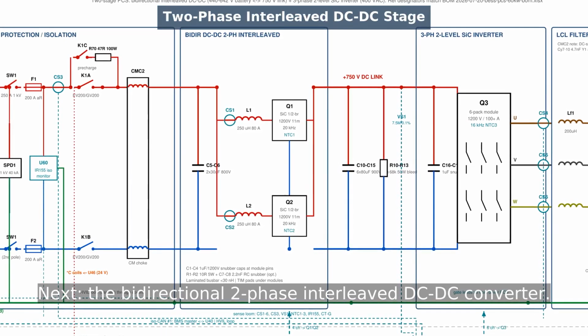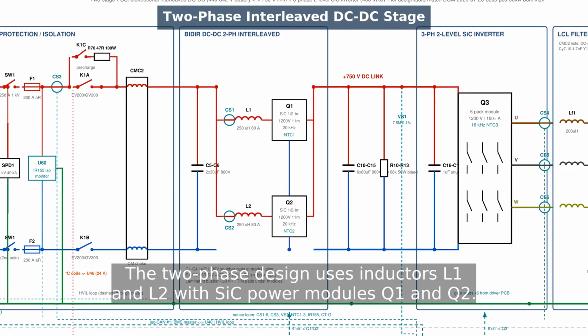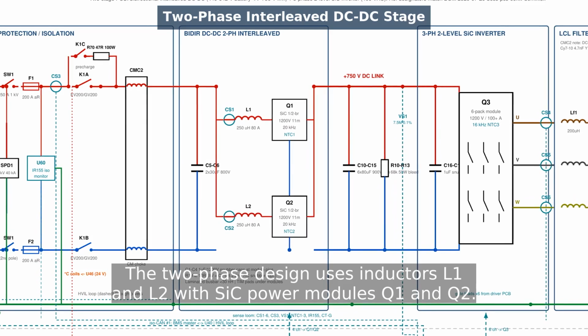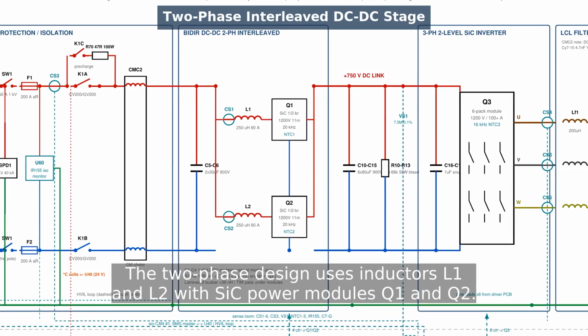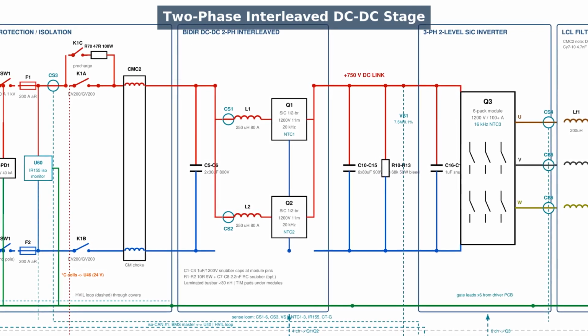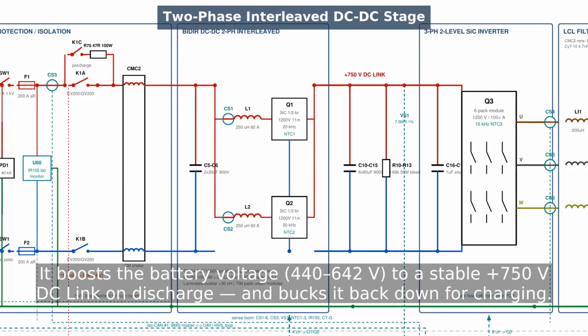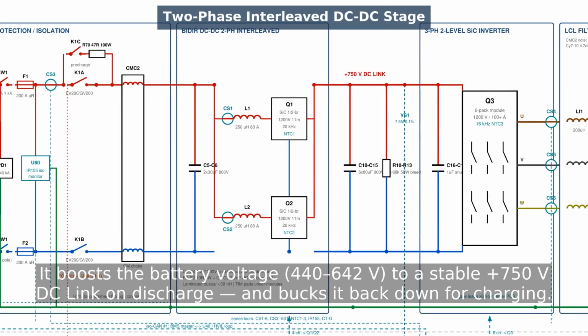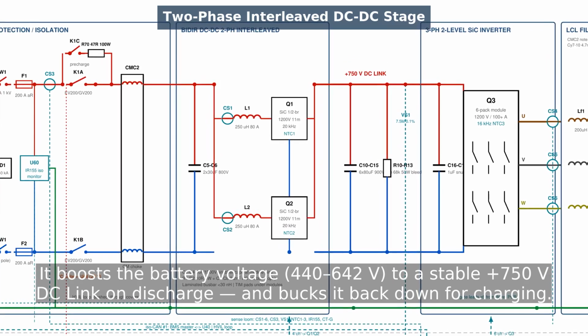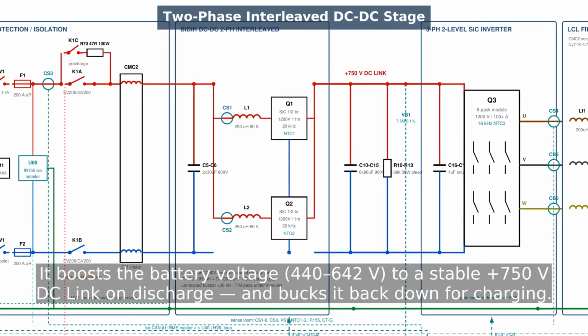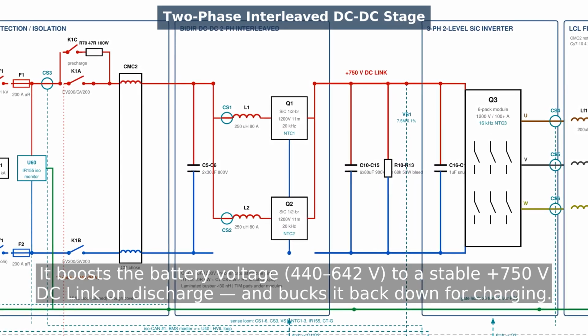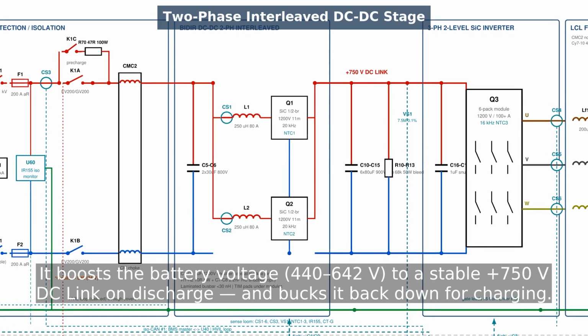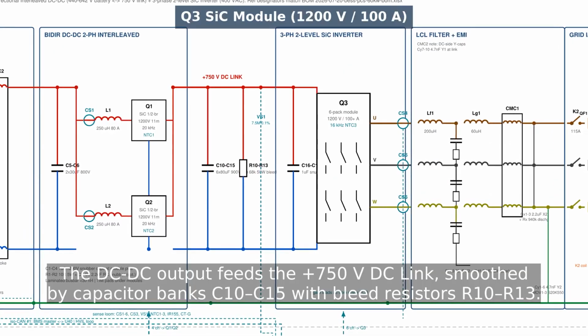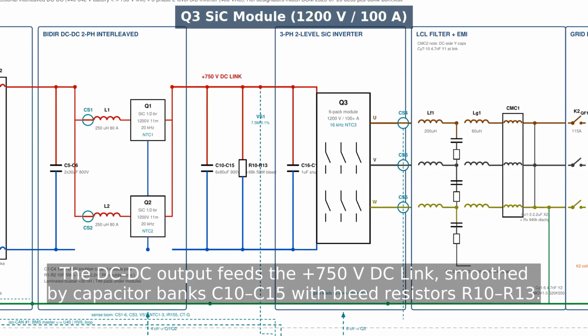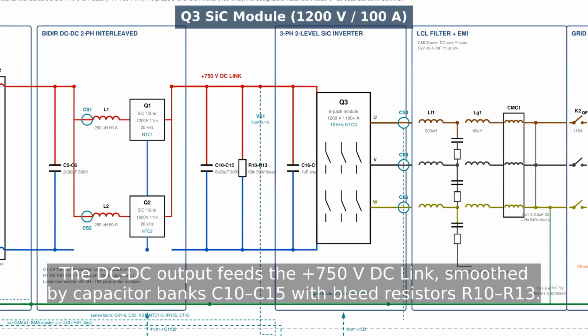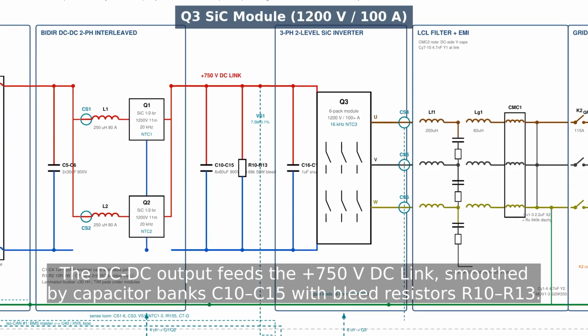DC to DC converter. A two-phase interleaved design using inductors L1 and L2 with silicon carbide power modules Q1 and Q2. The unit steps up the fluctuating battery voltage of 440 to 642 volts to a stable 750 volt DC link during discharge, and steps it down during battery charging. The 750 volt DC link is smoothed by decoupling capacitor banks C10 through C15 and bleed resistors R10 to R13.